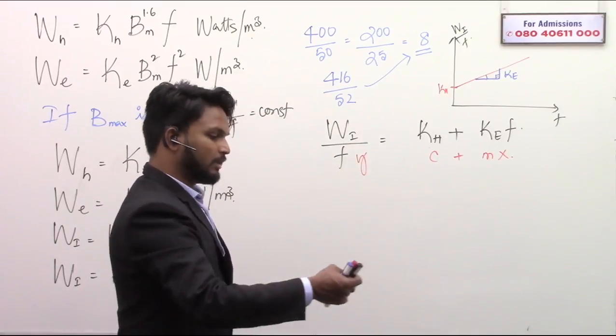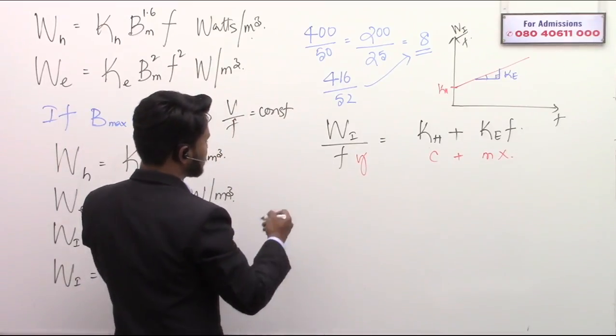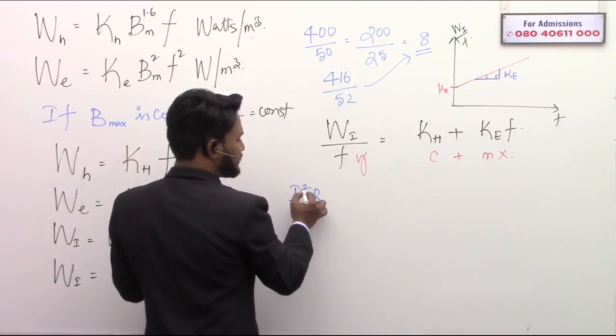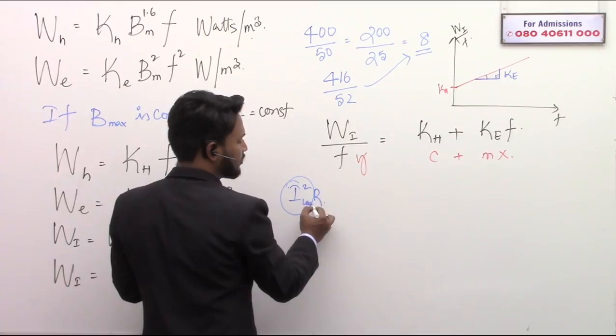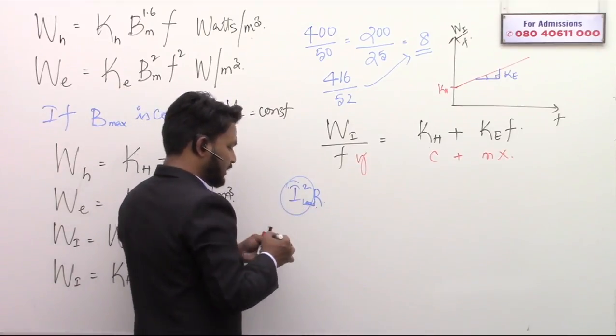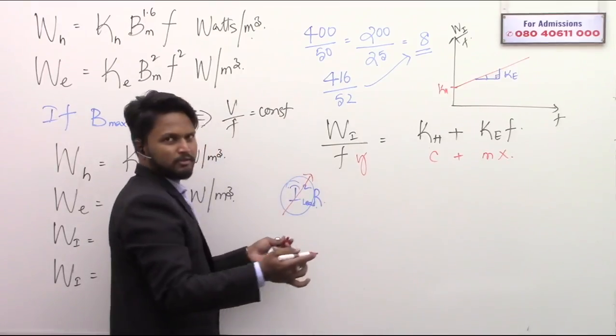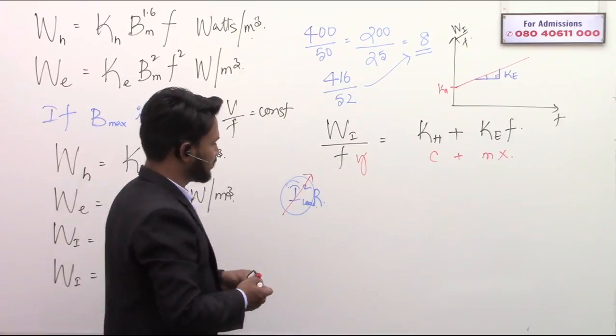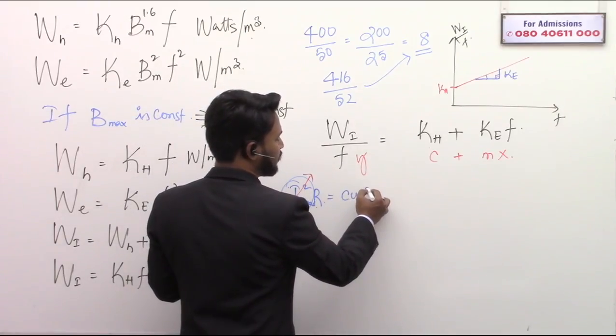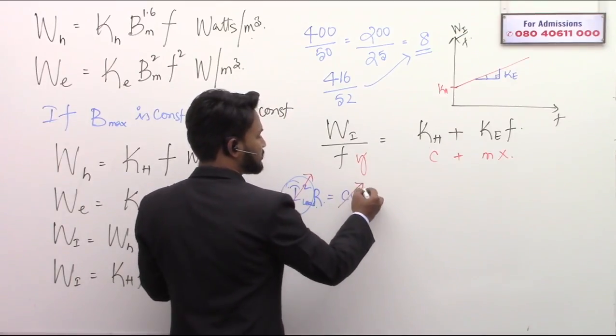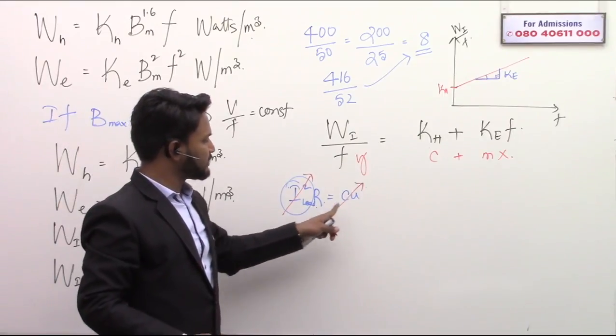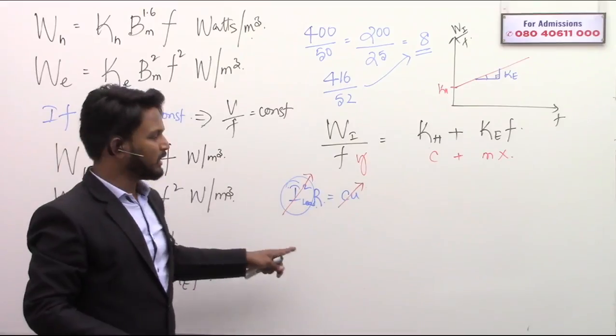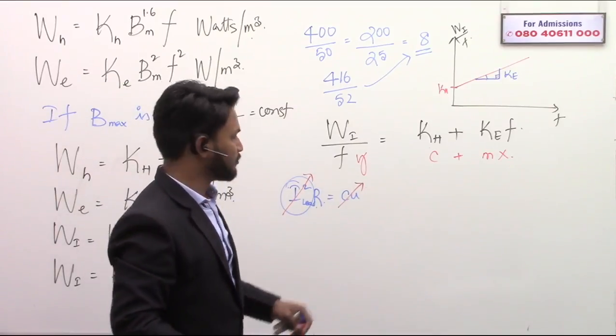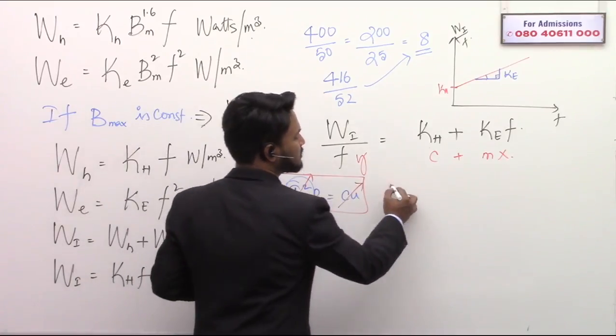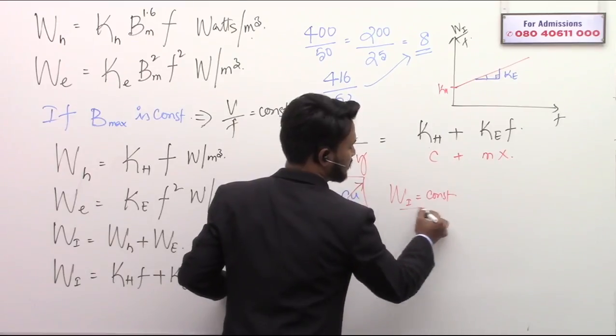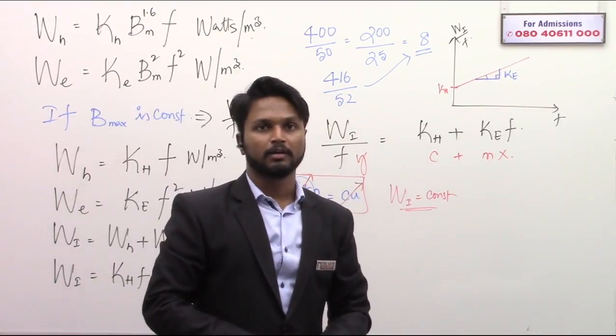Copper losses are I square R losses. This I is load current. If load current is varied - and load current is always variable - copper losses will also vary. This arrow mark I'm putting here to indicate variation. So copper losses are variable with respect to load current, whereas irrespective of load current, the iron losses are the same - they do not depend on load current at all. That is the reason why they are called constant losses, because iron losses do not depend on load current.